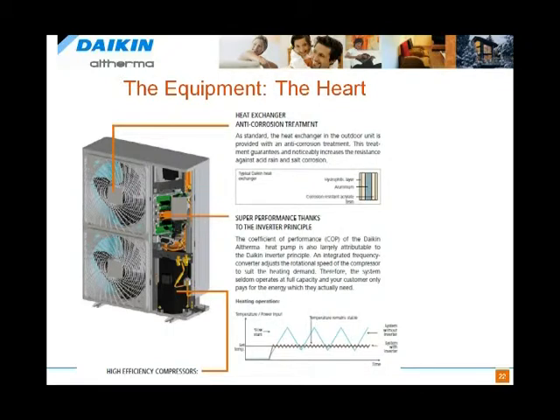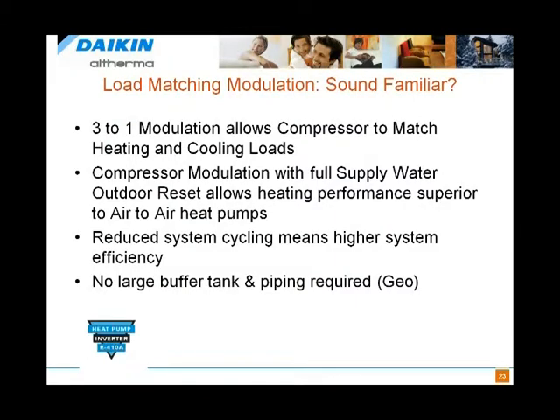This characteristic is also very important for integration with solar electric systems in a net zero or otherwise design, because we don't have that on-off surges that occur with on-off systems and draw so much energy. So it's in a 3-to-1 or 4-to-1 configuration, so we can match loads. Also, the unit comes with sensors and is set up with a sensor attached to the outdoor unit for doing outdoor reset. Highly recommend doing outdoor reset with these units. You can extract much greater efficiencies doing so, even on top of the inverter technology available here.